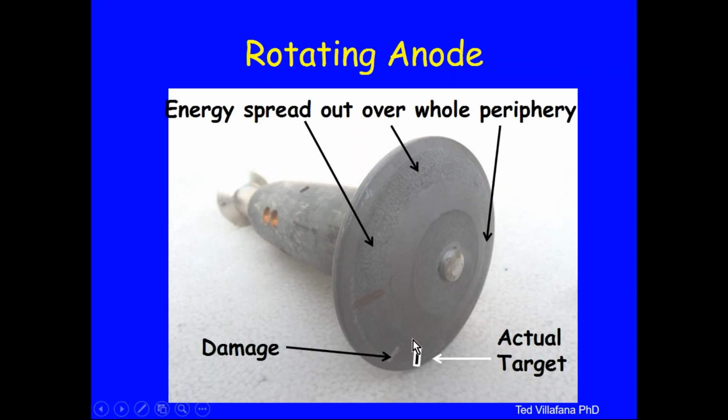That looks like a damaged region where there's not a full-fledged crack, but the heat was such in that region that little holes, or this whole little region, was burnt into the target, and out comes oxygen. There's always oxygen in metals, and whenever you break the surface of that metal, now you have oxygen coming out, and it could be a minuscule amount of oxygen, but enough to oxidize the filament, and pop goes the filament.